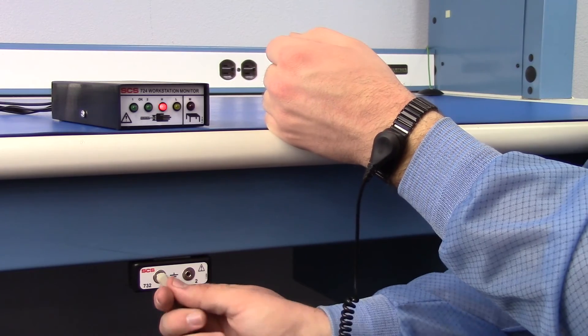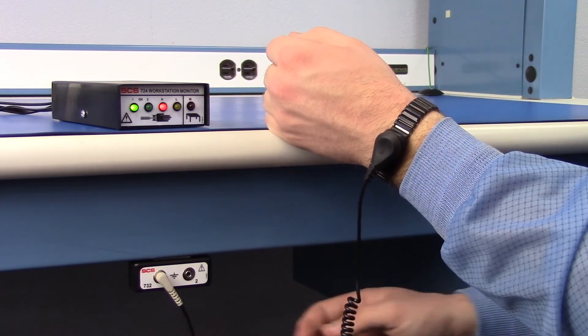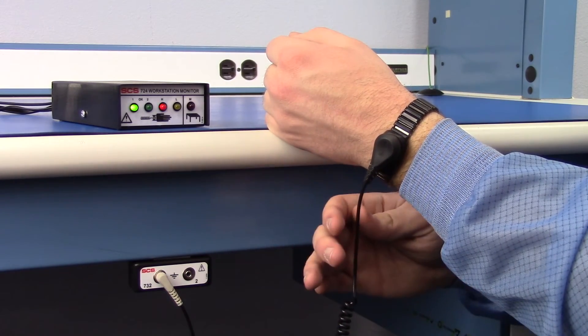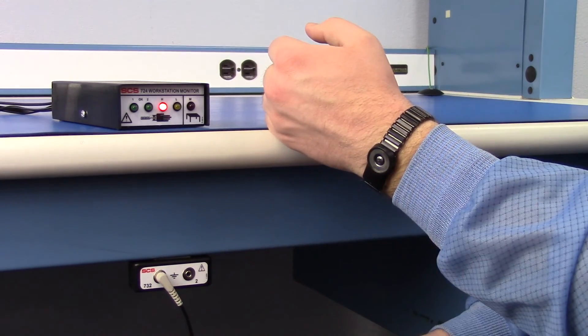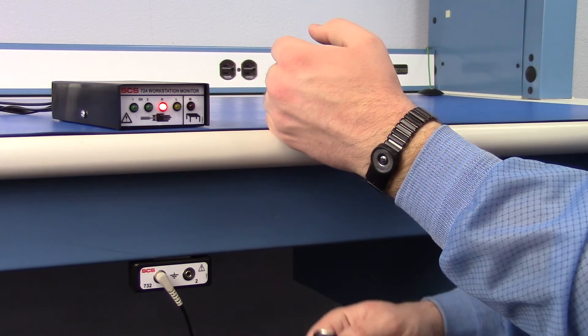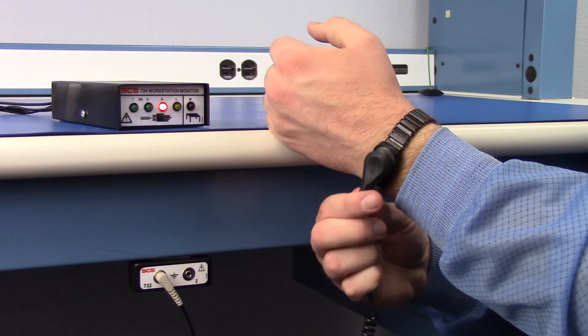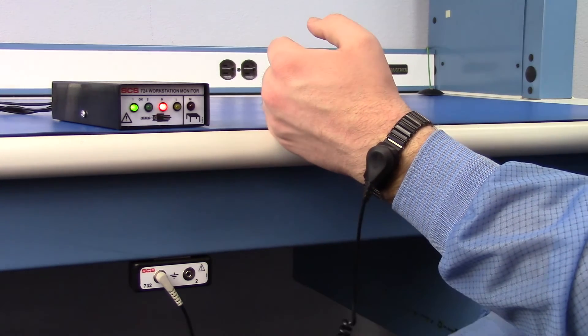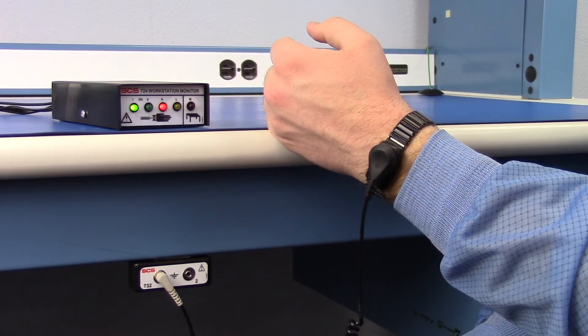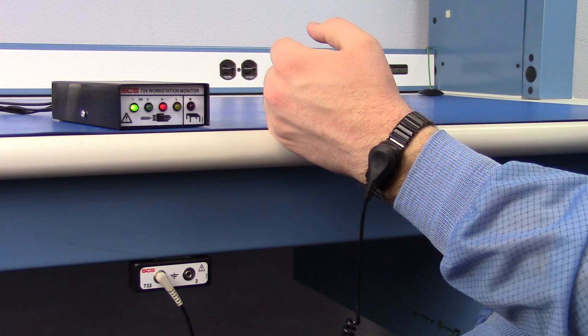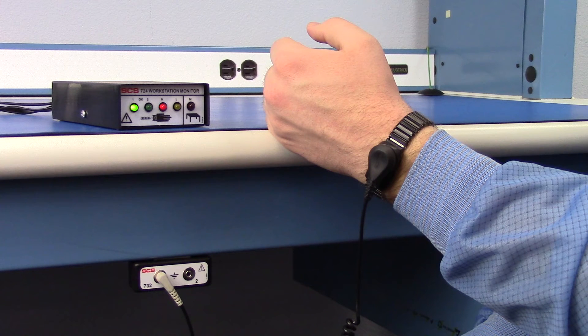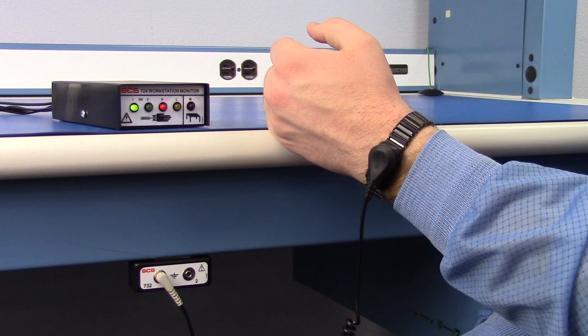The SCS 724 Workstation Monitor is now ready to monitor an operator. Fit a dual-wire wrist strap snugly to the wrist and plug its wrist cord into operator remote jack number one. The operator is now grounded and monitored for connectivity and resistance range. Use operator remote jack number two when a second operator is to be monitored at the workstation.